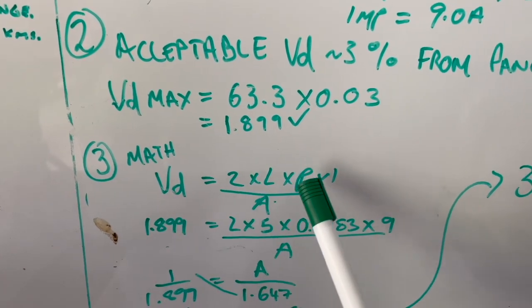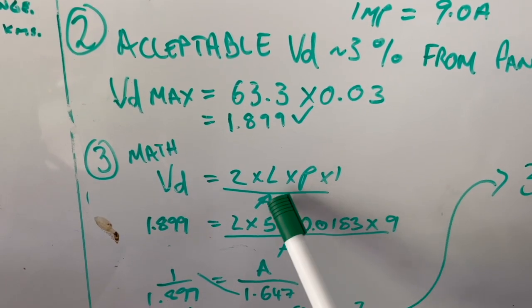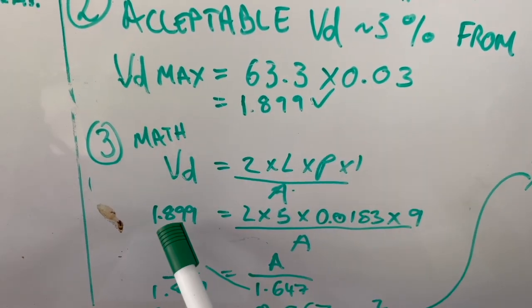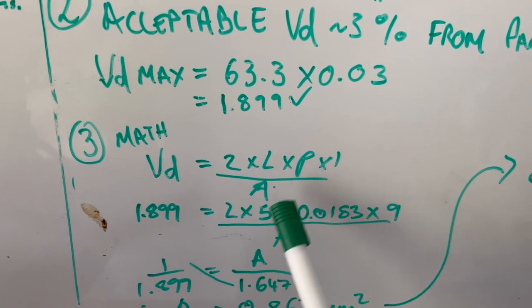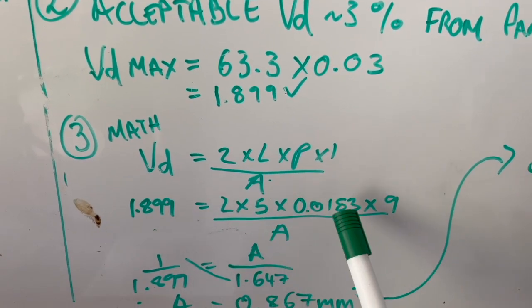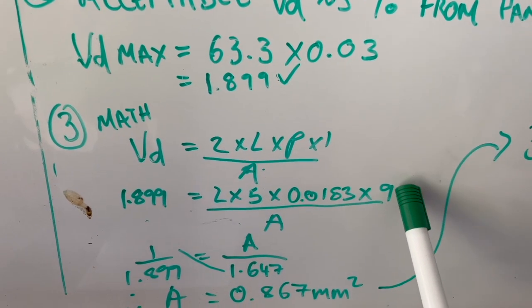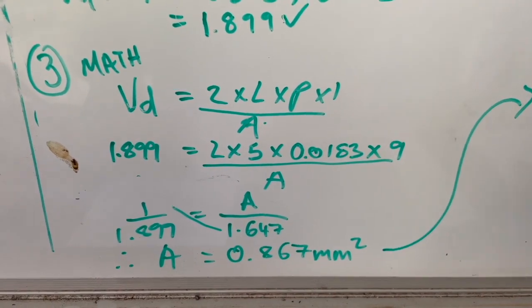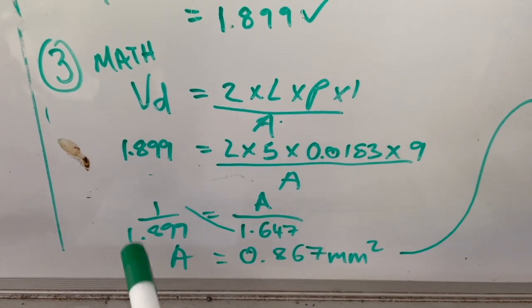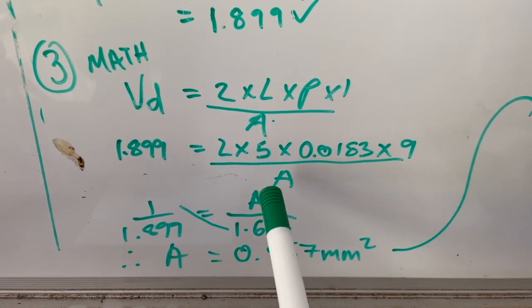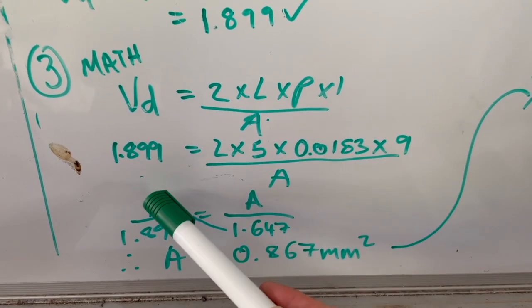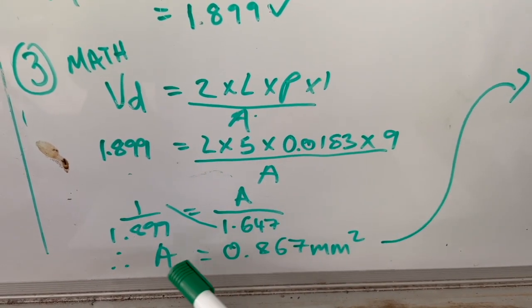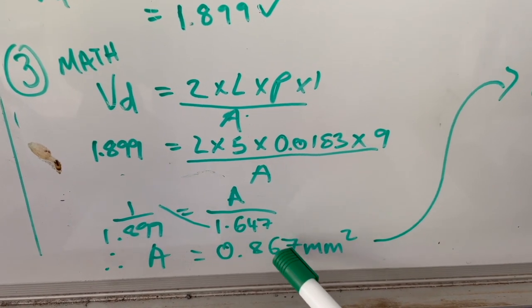Now it's just math, grab that formula. VD equals 2 times L times Rho times I over A. Plug in the numbers, so we've said voltage drop accepted is 1.899. We know all those figures. 2 times 5 times by resistivity times by max of amp is 9 over A. Go to some quick math, flip both sides. So it's 1.647 divided by 1.899 equals area equals 0.867 millimeters squared.